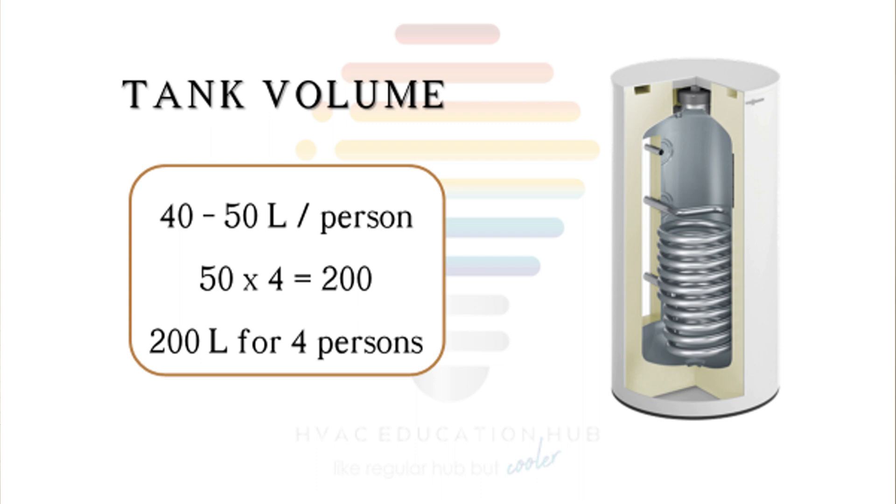Approximately 40 to 50 liters per person in your household is a rough calculation to determine how big your domestic hot water tank must be. In our example, we'll have four persons and a 200 liter hot water tank.